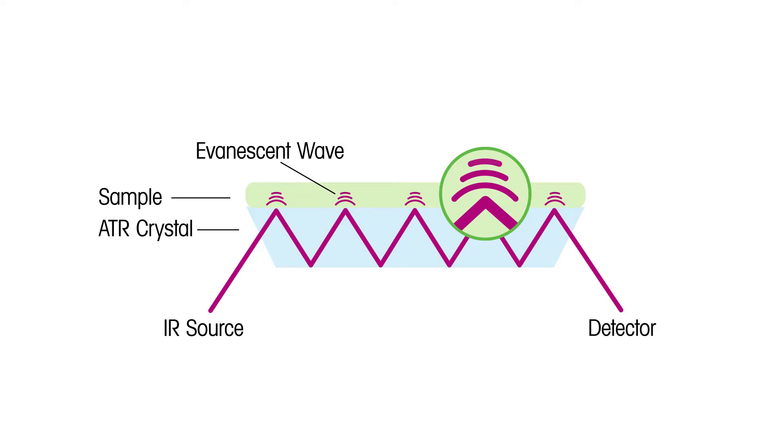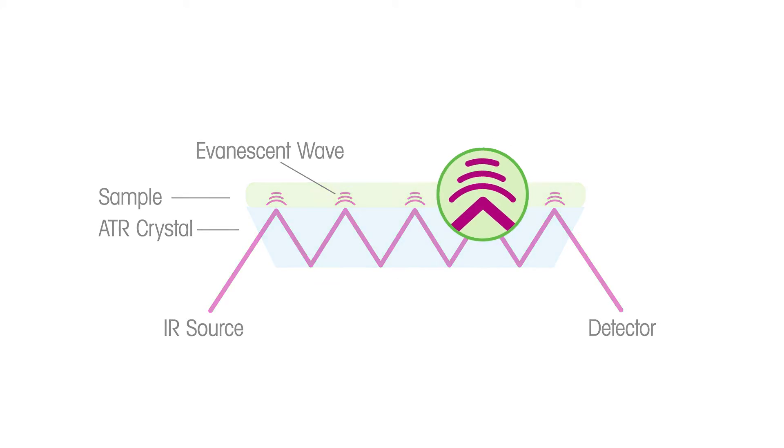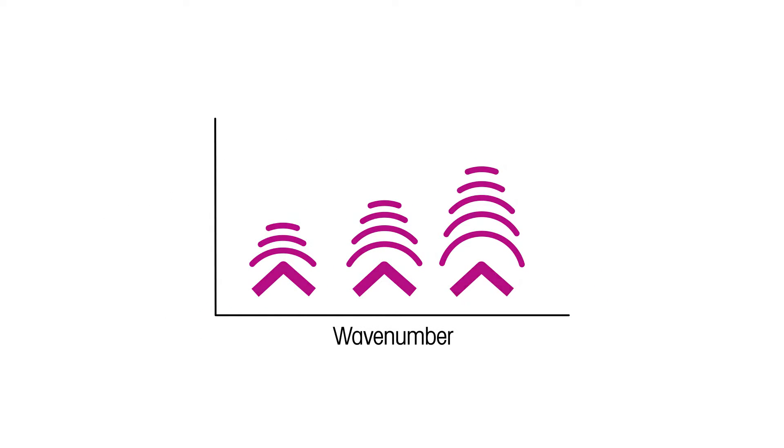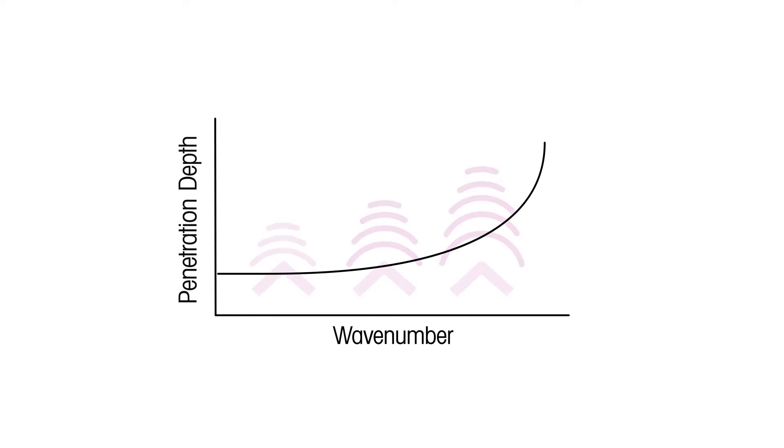First is the wavenumber being used. Because penetration depth varies with wavenumber, it is not constant across the whole spectrum being collected. The depth of penetration increases the lower your wavenumber is. This will mean that peaks down by 400 wavenumbers will have a higher peak intensity than the peaks at 4000 wavenumbers, when compared to a transmission experiment.